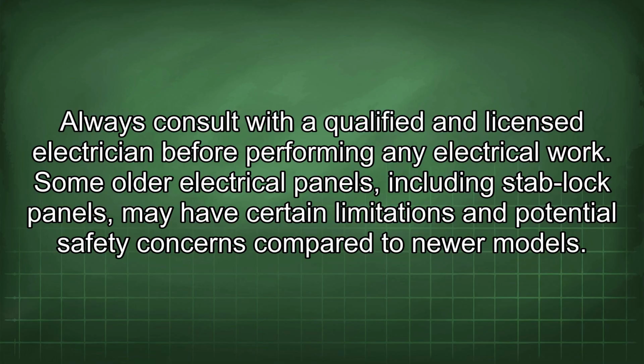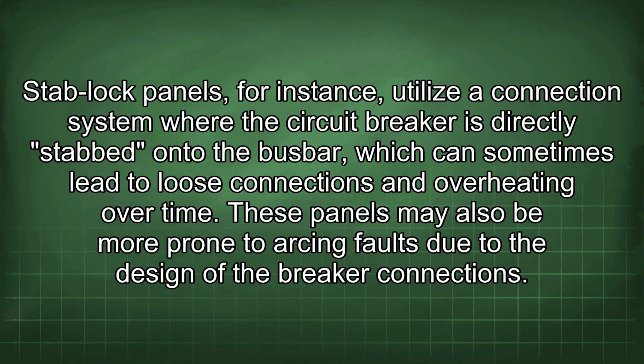Some older electrical panels, including stab lock panels, may have certain limitations and potential safety concerns compared to newer models. Stab lock panels, for instance, utilize a connection system where the circuit breaker is directly stabbed onto the bus bar, which can sometimes lead to loose connections and overheating over time. These panels may also be more prone to arcing faults due to the design of the breaker connections.